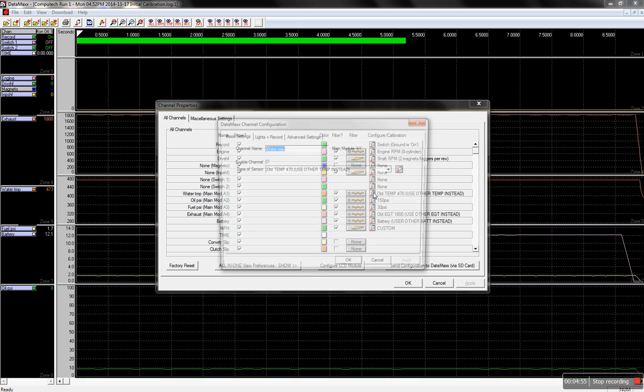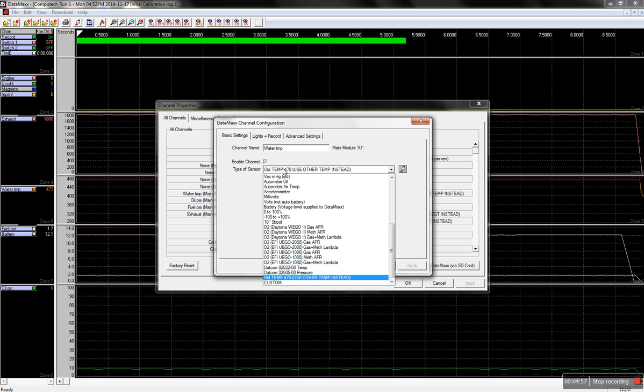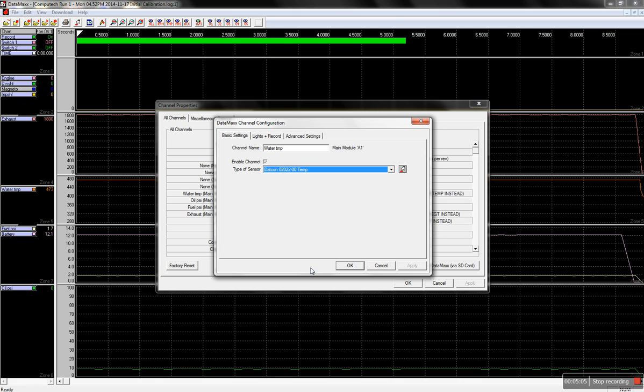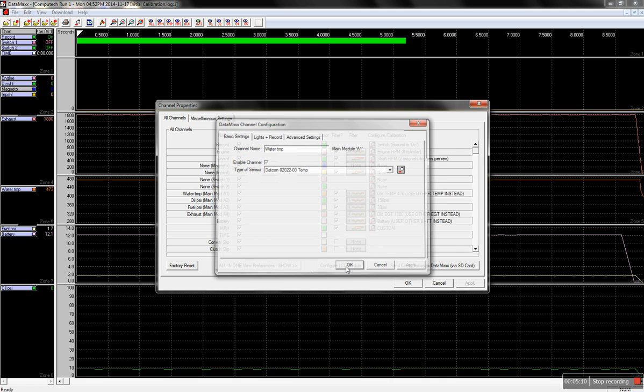To do that, click on the calibration button and from the type of sensor drop-down list, go ahead and select the DATCON 02022-00 temp. This is the calibration for any of the one-wire temp sensors. So we're going to go ahead and change the type of sensor and hit OK.